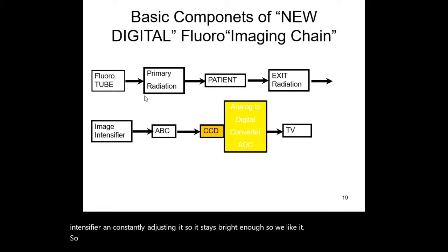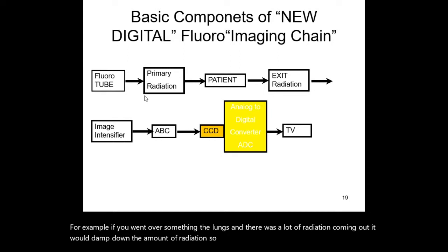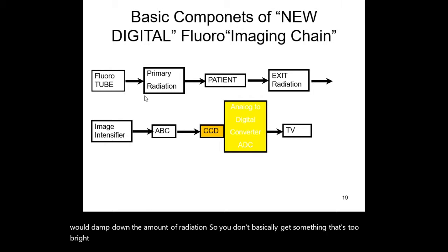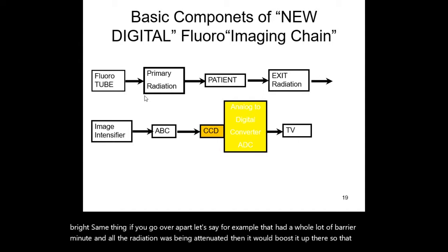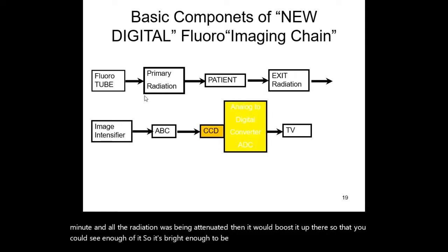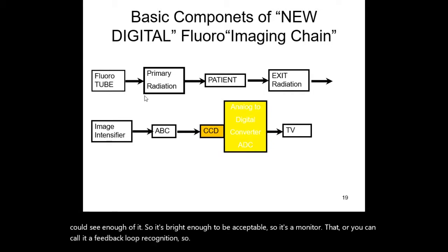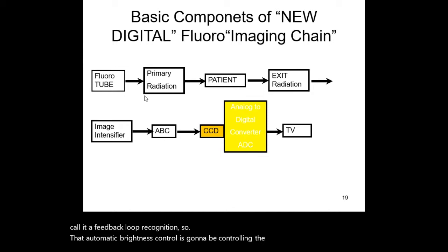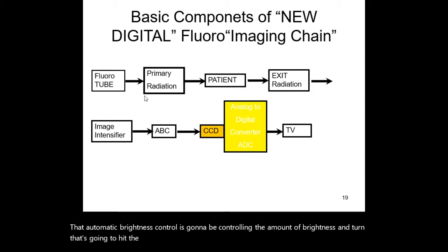So, for example, if you went over something like the lungs, and there was a lot of radiation coming out, it would damp down the amount of radiation so you don't basically get something that's too bright. Same thing if you go over a part, let's say, for example, it had a whole lot of barium in it and all the radiation was being attenuated, and it would boost it up there so that you could see enough of it so it's bright enough to be acceptable. So it's a monitor of that, or you can call it a feedback loop mechanism. So that automatic brightness control is going to be controlling the amount of brightness in turn that's going to hit the CCD. Okay, and the CCD, remember, is charge coupled device. That sort of takes the place, in a sense, of our camera.